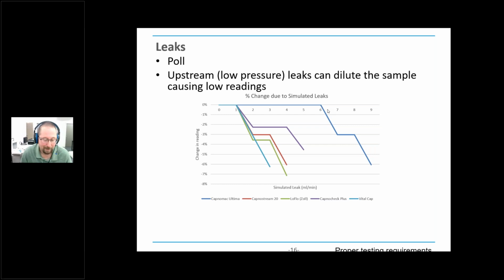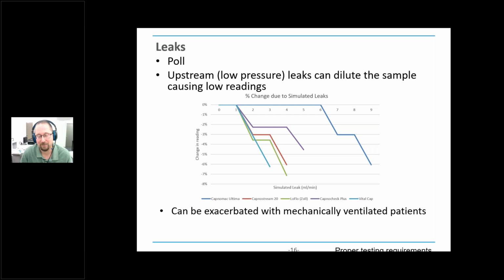So what happens though is you might recalibrate it with this leak and it will calibrate just fine. And so maybe it's working fine for some of the normal cases, but as soon as you put it on a mechanically ventilated patient, now all of a sudden the use case is totally different and you've got higher pressures going on, and now you're actually going to have problems there too.